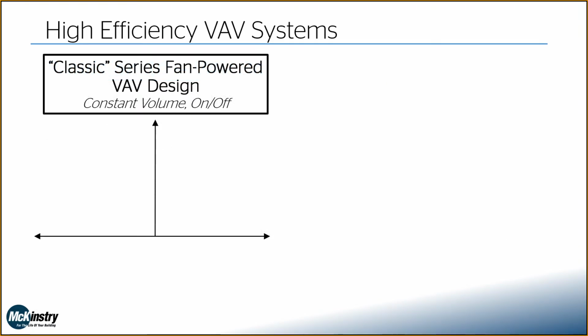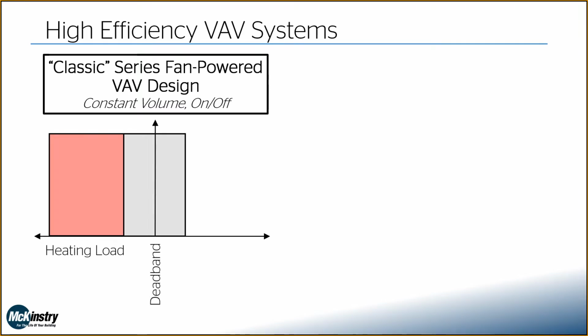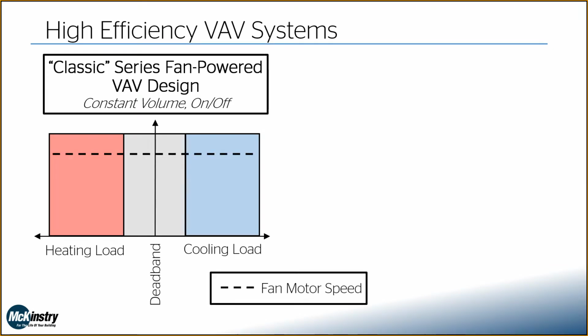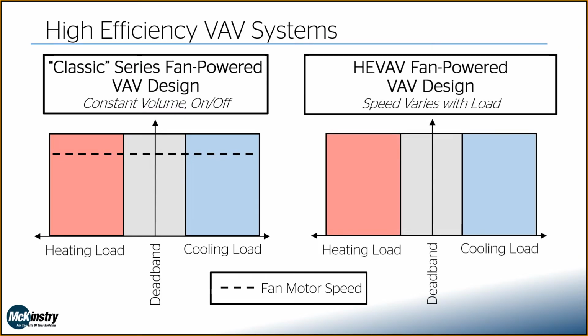To visualize that, here's a classic series fan-powered VAV design. We have our three operating modes: heating, deadband, and cooling. In classic design, the fan motor speed is just constant. Anytime the space is in occupied mode, that fan is running full out. But with high efficiency VAV, we need to vary that fan speed with the heating load. At a high heating load, our fan speed will be high, and it'll drop off as we approach the deadband. In the deadband zone, we're at some minimum speed, and then it increases on the cooling side as our cooling load increases.